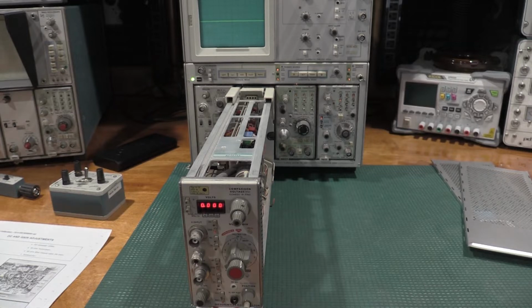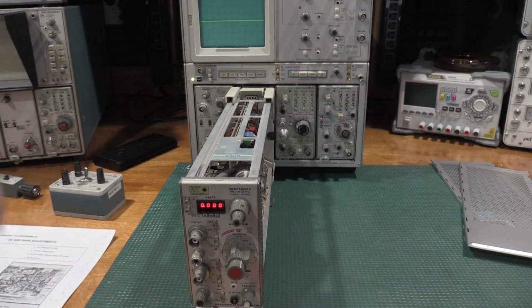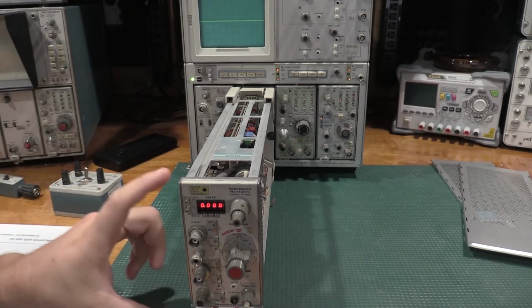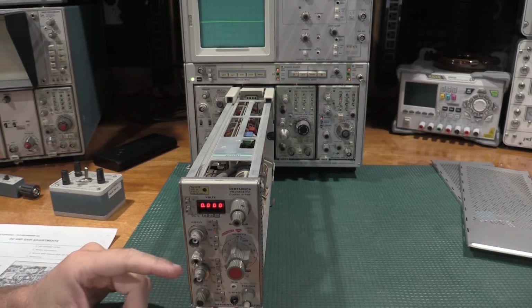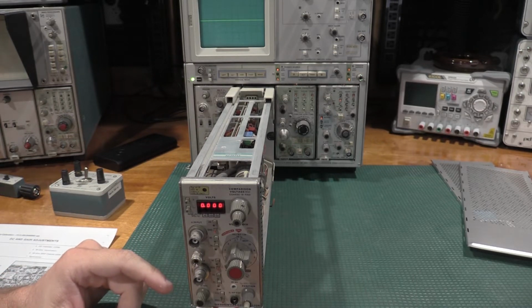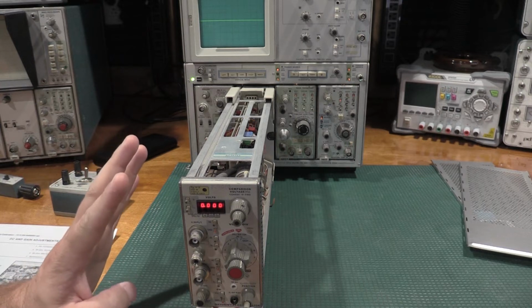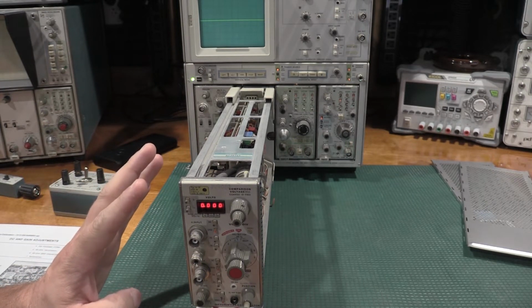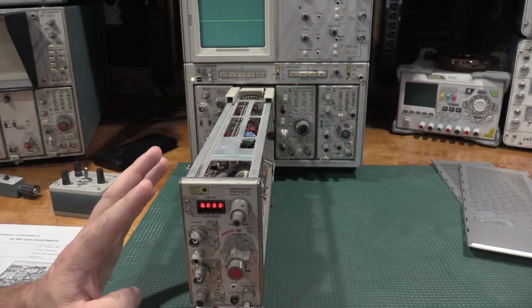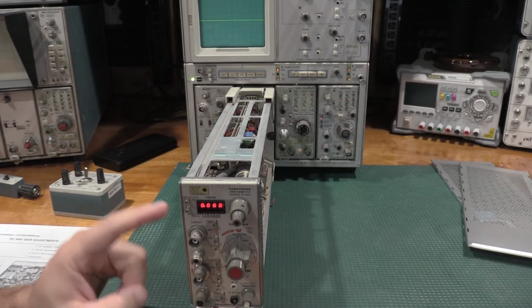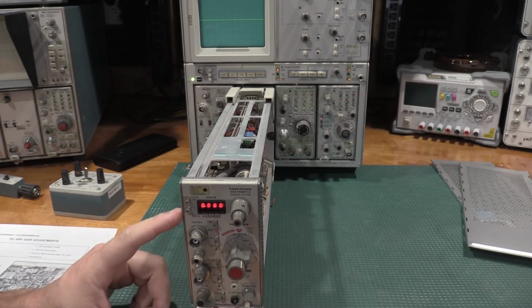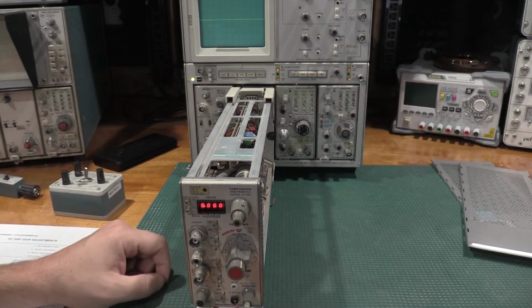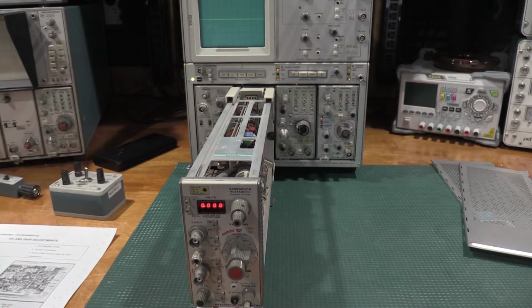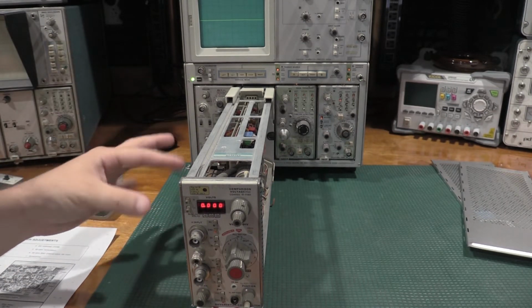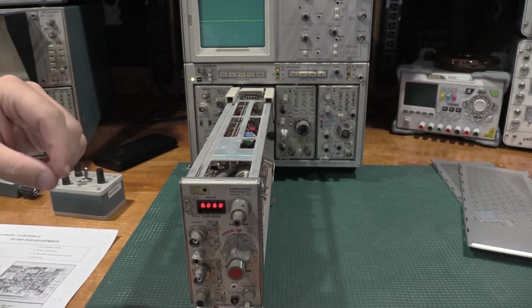Typically, I would do these in a scope as I was going through the alignment procedure. However, for this particular plug-in, these need to be adjusted. There are 4 adjustments: the variable balance, the step attenuator balance, the 10x balance, and the gain adjustment that need to be done every time you move this to a different scope. It's affected by the power supplies in the frame, how well they're in tolerance with each other, because this is using plus and minus supplies.